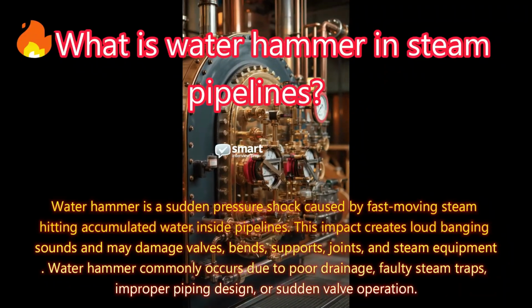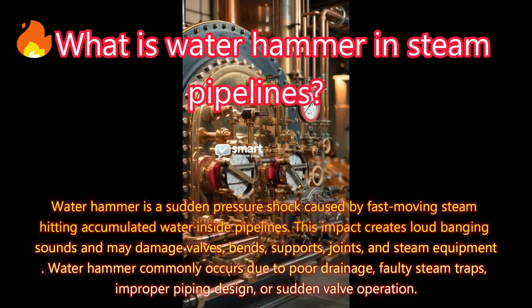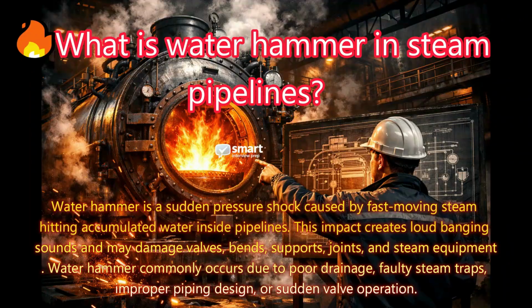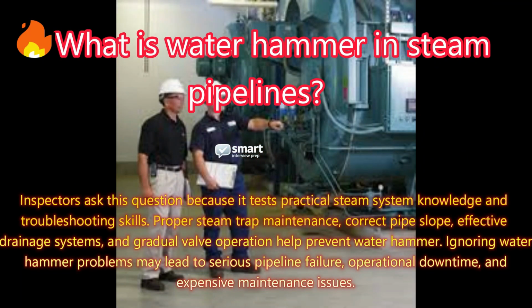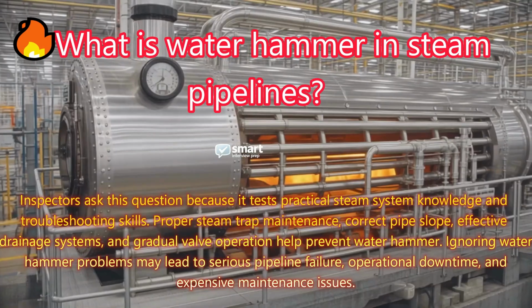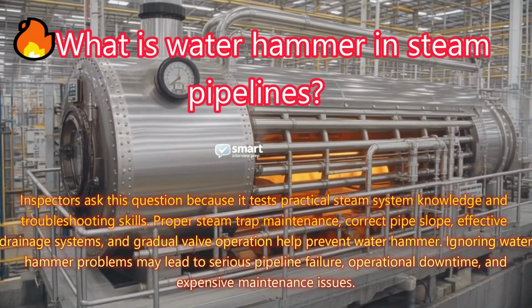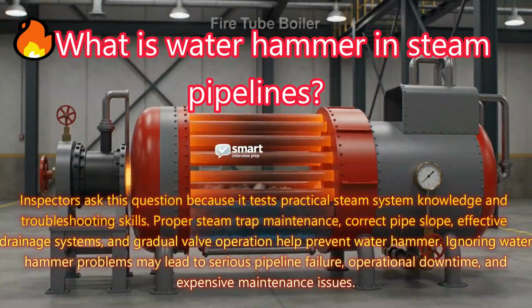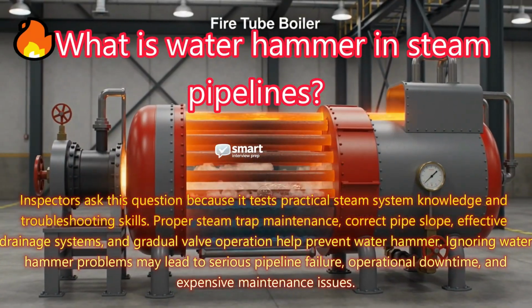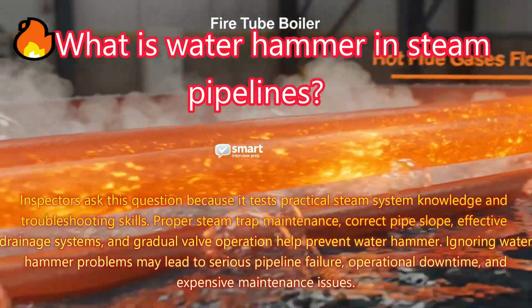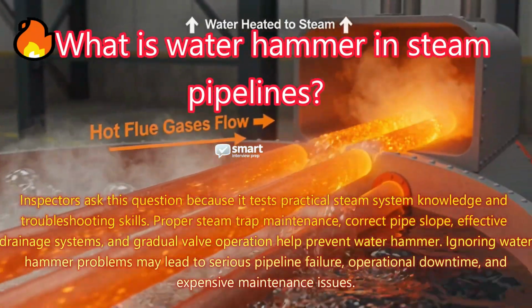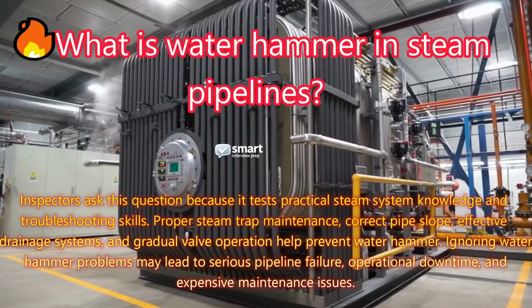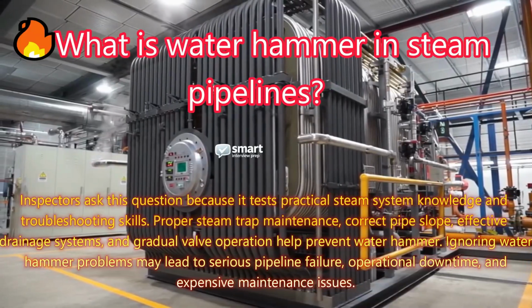Water hammer commonly occurs due to poor drainage, faulty steam traps, improper piping, design, or sudden valve operation. Inspectors ask this question because it tests practical steam system knowledge and troubleshooting skills. Proper steam trap maintenance, correct pipe slope, effective drainage systems, and gradual valve operation help prevent water hammer. Ignoring water hammer problems may lead to serious pipeline failure, operational downtime, and expensive maintenance issues.